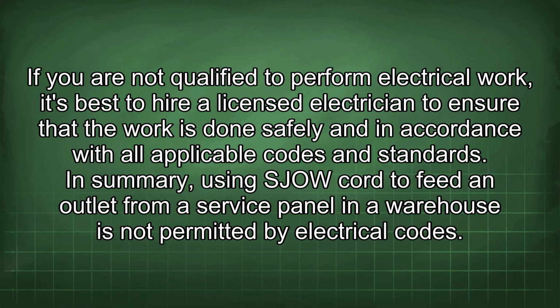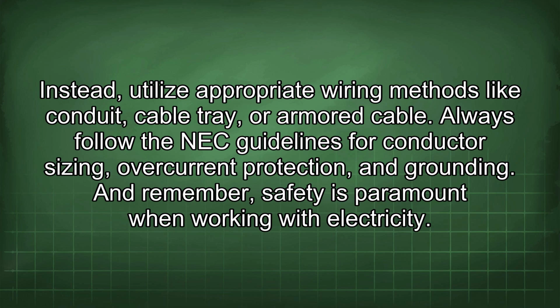In summary, using SJOW cord to feed an outlet from a service panel in a warehouse is not permitted by electrical codes. Instead, utilize appropriate wiring methods like conduit, cable tray, or armored cable. Always follow the NEC guidelines for conductor sizing, overcurrent protection, and grounding. And remember, safety is paramount when working with electricity.